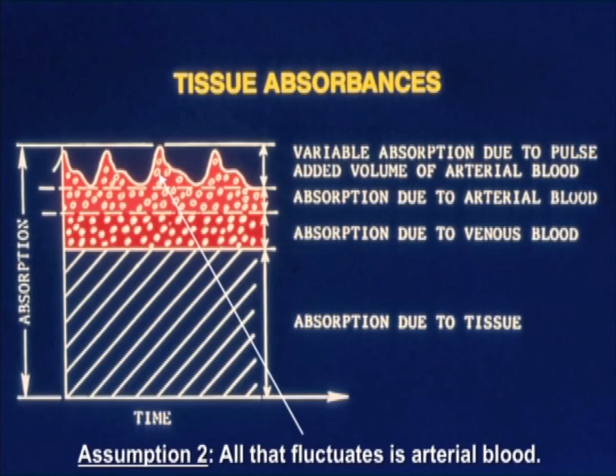Okay, the final step, how do you get from there to saturation? Well, consider 2 extremes. This was again Aoyagi's reasoning. We have a patient with 100% saturation, happy face. Remember here are the dye dilution curves, just to remind you, I know those are very small, but remember the oxyhemoglobin has a low absorbance in the visible red, and therefore you'll get low pulsations in the visible red when there's a lot of oxyhemoglobin present, right? The reduced hemoglobin has a high absorbance in the red. The oxyhemoglobin conversely has a high absorbance in the infrared, and so you get large pulsations in the infrared.